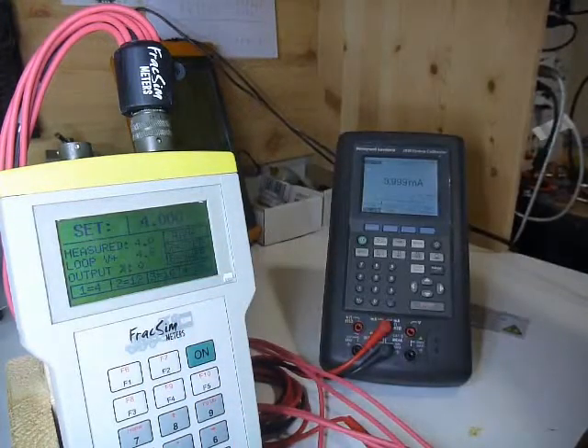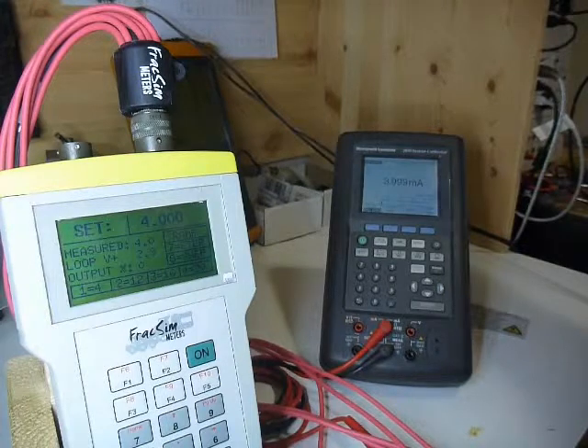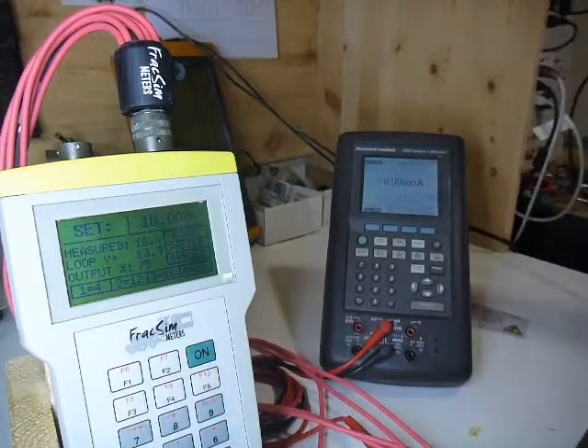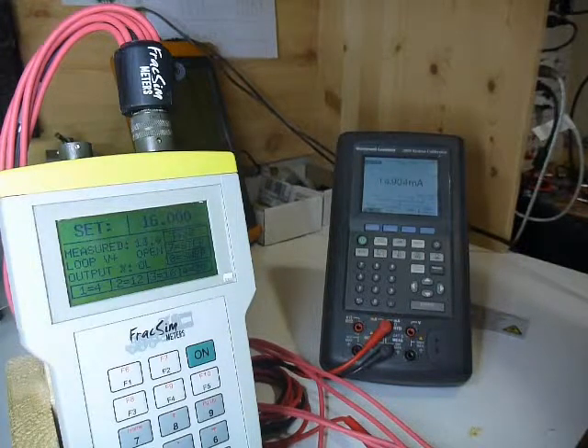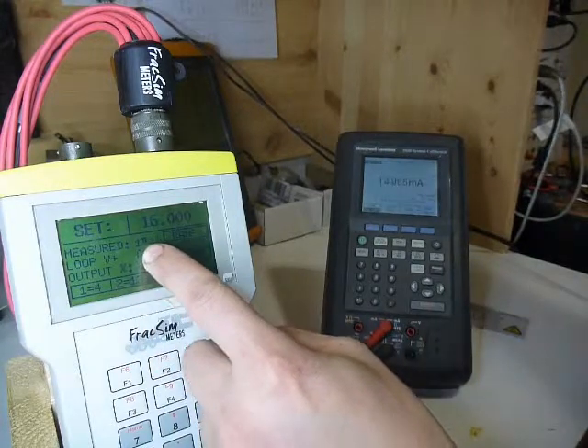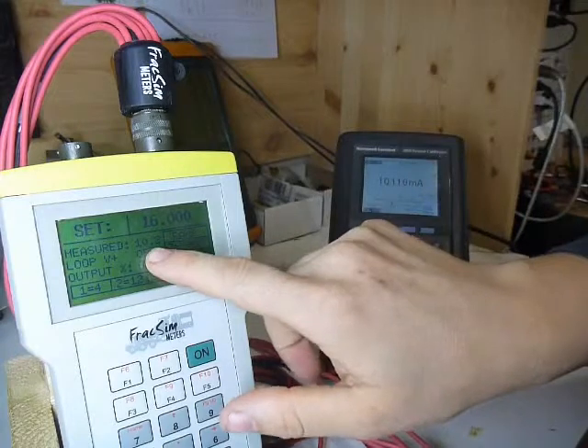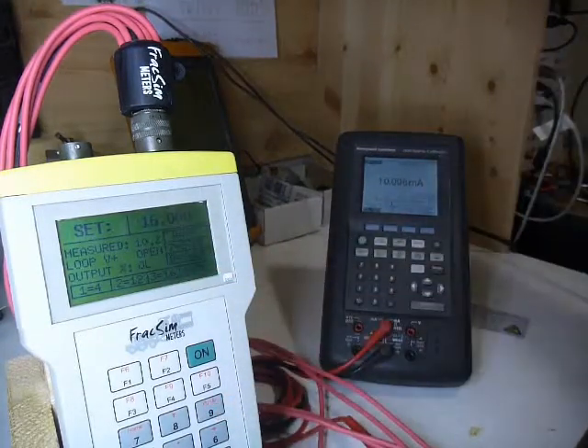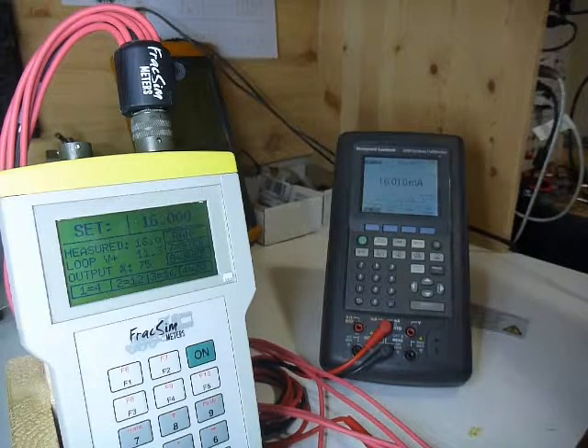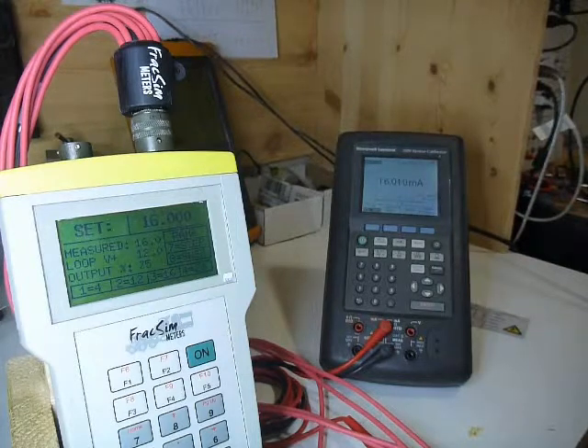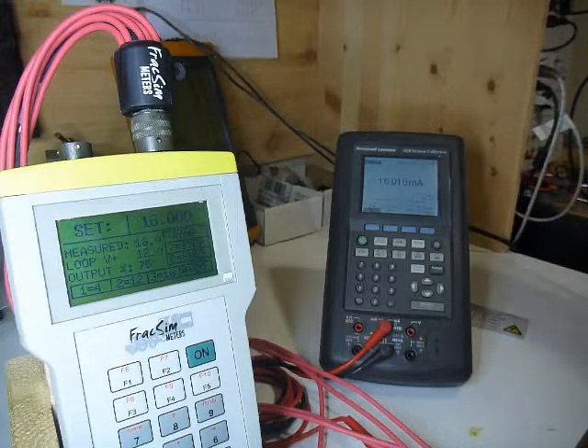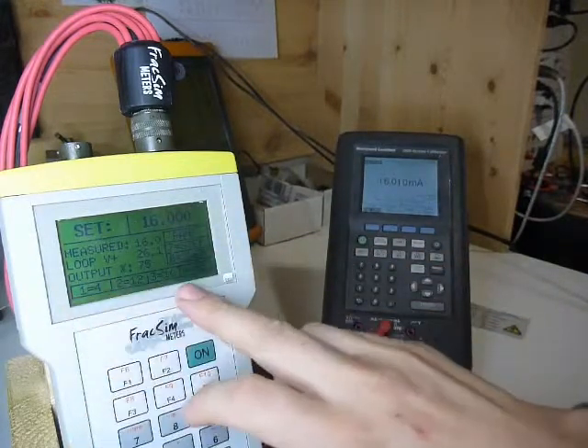And also you'll see, if we drop the loop voltage low enough, that I'm going to have to increase the target a little bit, the actual measured current starts to drop off when your voltage is too low. You see this moves to open, and then the actual measured current is showing, and we do not right now have enough voltage. So you can use that for troubleshooting as well. But like I said, if you're working on a loop, the minimum you should see is 12, and most systems that I've seen built in the last decade are all set up for 24 volts, not 12 volts, which in that case you would see it way up here. And then all the options, same options apply.